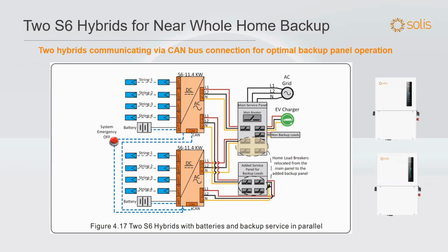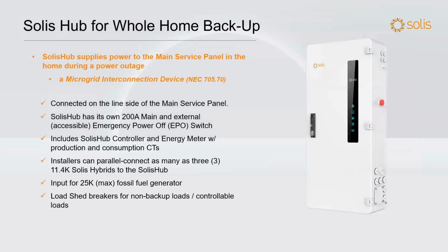Another thing I wanted to point out here is the system emergency off button. This connects to your inverters, and it's a beautiful thing for firemen, who now know it's not just about rapid shutdown, but also about the potential for batteries powering up this backup load panel. So even when I hit that big red button to initiate rapid shutdown, I haven't really shut down the system, have I? So if I can get a button that shuts down the PV, but also the battery and the inverter, that makes me more confident walking into a house without a lot of DC conductors running through it live.